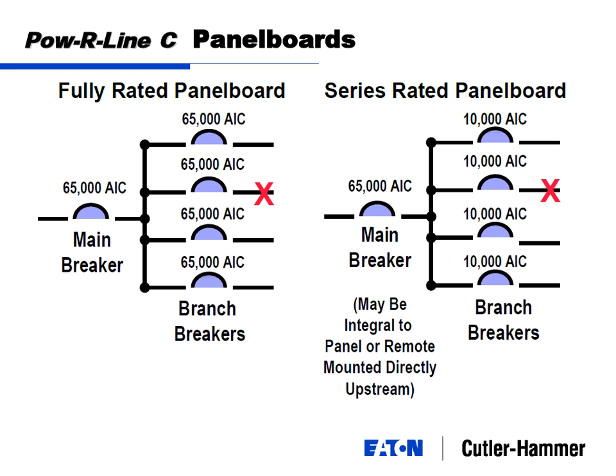And the only way we can get by with what I would call providing an underrated device is because we took these breakers to UL, put them on a bench test, blew 65,000 amps through them, and proved that the breakers will do the job. And conceptually, how can this thing see 65,000 amps? That just doesn't make sense if it's only tested for 10,000 amps.